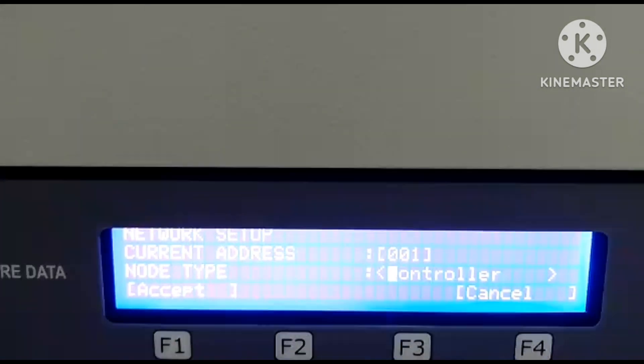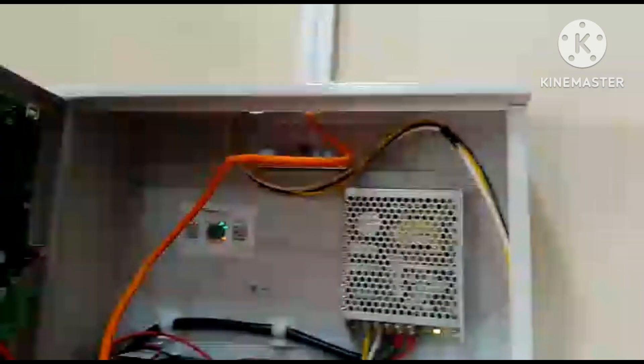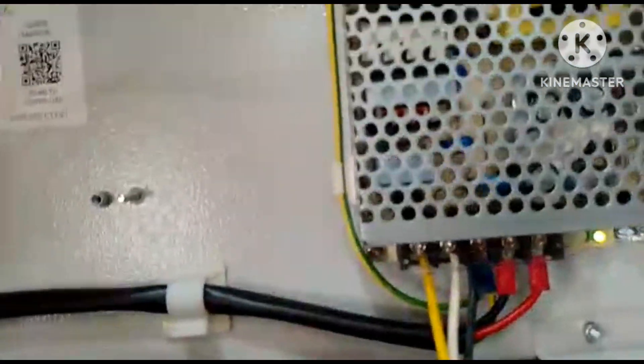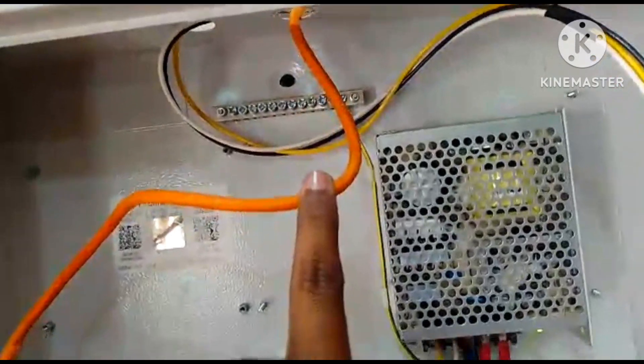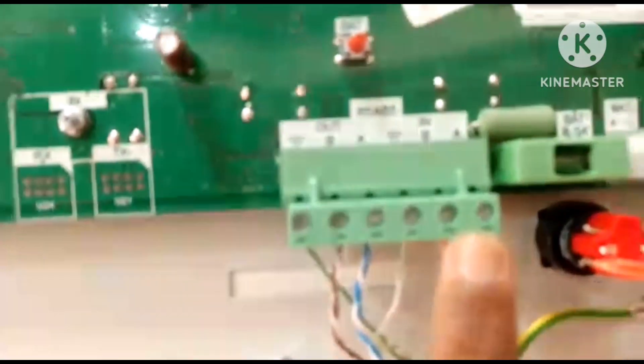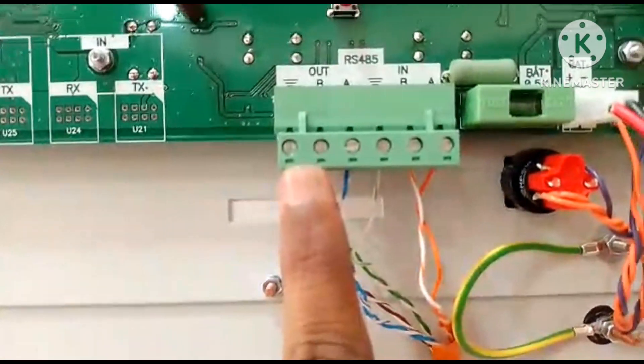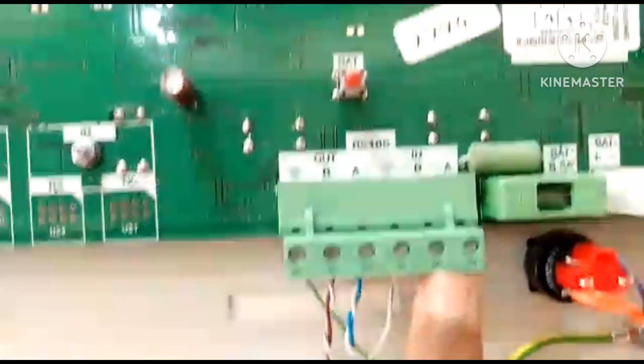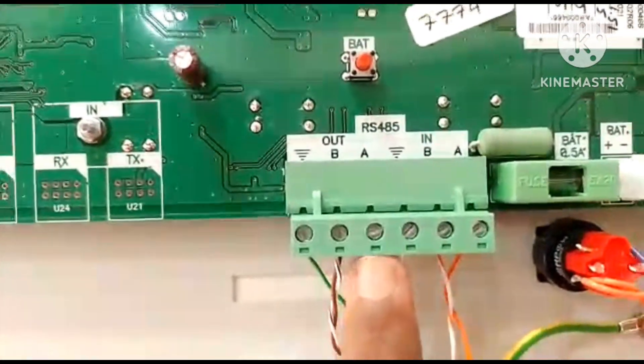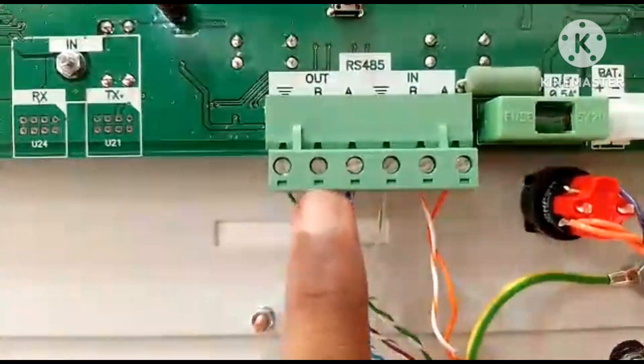Now we are in Wadi Villa at the repeater panel. Here is the termination for this repeater panel. The power cable is connected here, and the Cat6 cable coming from the main panel is connected here as well. There is an IN and OUT — first we'll talk about IN. IN here means the main panel's OUT, and OUT here means the main panel's IN. For IN we have cable A, cable B, and the earth cable — 3 cables total. Similarly for OUT we have A, B, network cable, and earth cable. Termination here is finished.